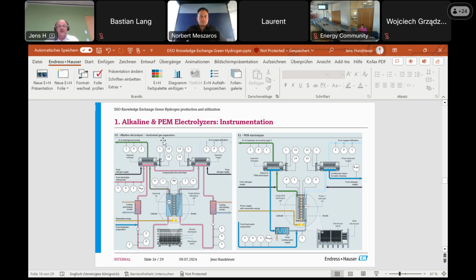Then we have different measurements in the separator. I'd like to show this measurement a bit. One customer said something we hadn't thought of - we have many standard measurements, some modified, but the customer wanted the differential pressure between the hydrogen and oxygen separator, meaning on one side the differential pressure measurement sees 100% hydrogen.